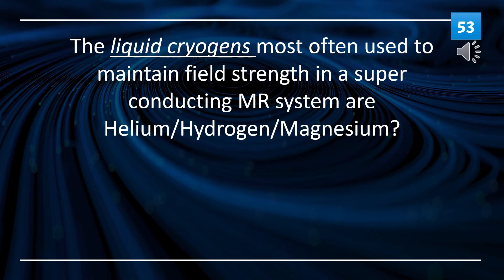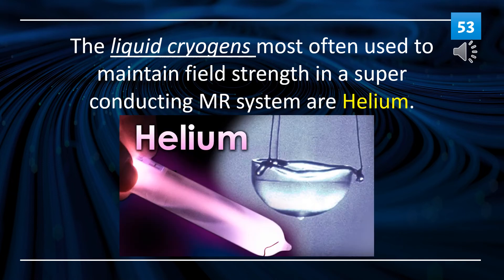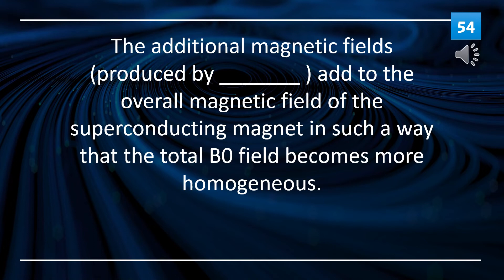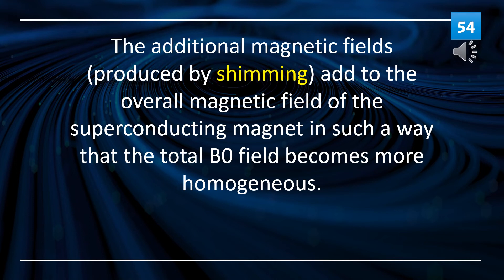The liquid cryogens most often used to maintain field strength in a superconducting MR system are helium. The additional magnetic fields produced by shimming add to the overall magnetic field of the superconducting magnet in such a way that the total B0 field becomes more homogeneous.